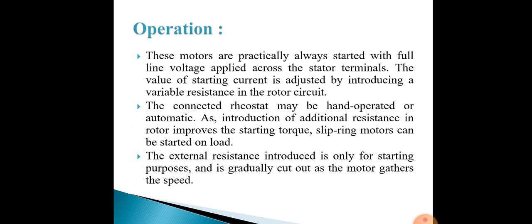This is the operation of the slip ring induction motor. We introduce additional resistance in the rotor circuit to improve the starting torque. Slip ring induction motors can be started on load. The value of starting current is adjusted by introducing the variable resistance in the rotor circuit.